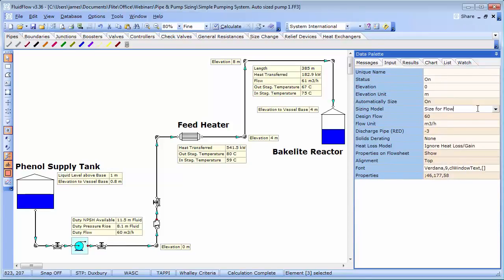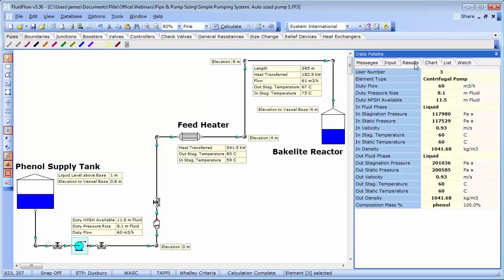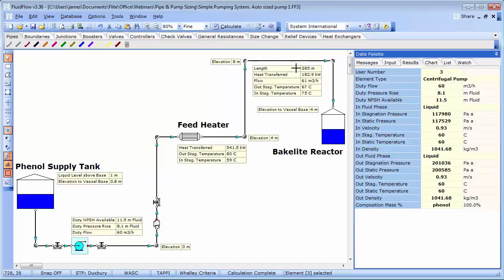The system loss calculation can be made quite easily using the automatically sized function which we just looked at earlier. We have set the design flow rate to 60m3 per hour. You could set the design duty pressure rise if the information were available. From this solution, we can see that the pump duty pressure rise is 8.1 metres of fluid. And the net positive suction head available in the system is 11.5 metres of fluid. We can also see that there is substantial heat loss in some of the pipes which we will revisit a little later.